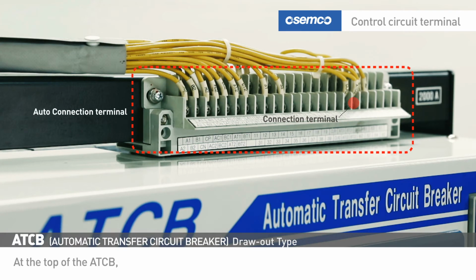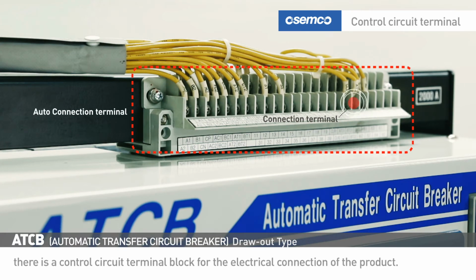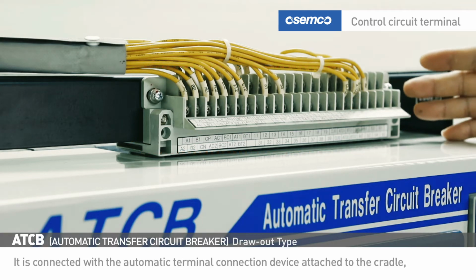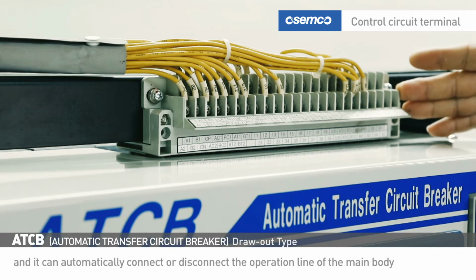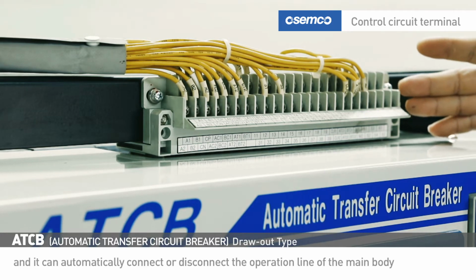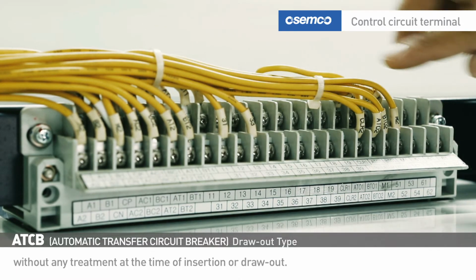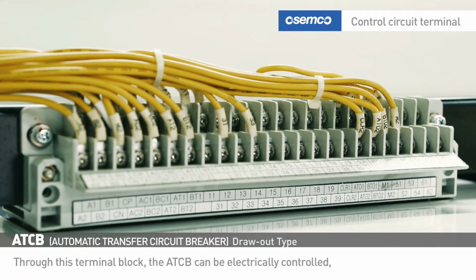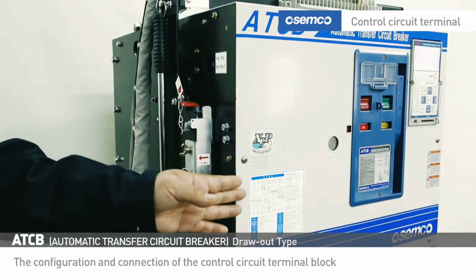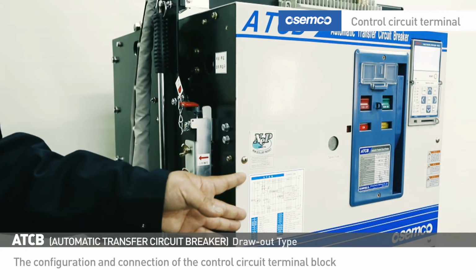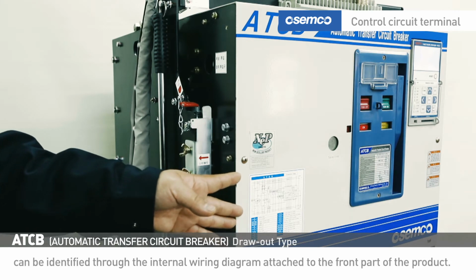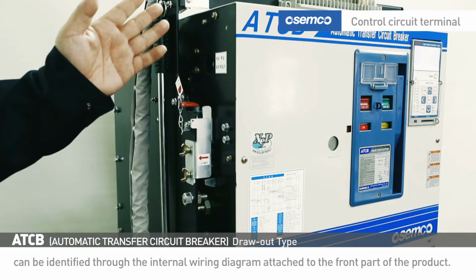At the top of the ATCB, there is a control circuit terminal block for the electrical connection of the product. It is connected with the automatic terminal connection device attached to the cradle, and it can automatically connect or disconnect the operation line of the main body without any treatment at the time of insertion or draw-out. Through this terminal block, the ATCB can be electrically controlled and the electrical status can be checked. The configuration and connection of the control circuit terminal block can be identified through the internal wiring diagram attached to the front part of the product.